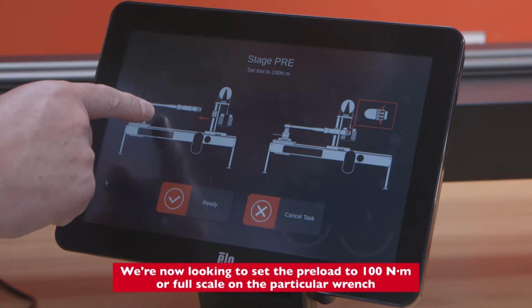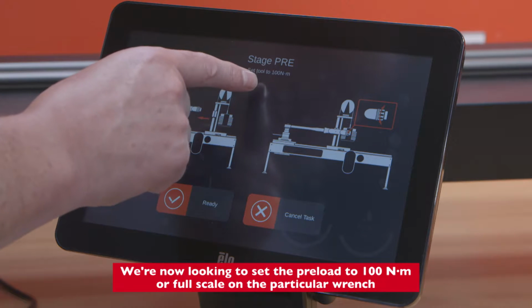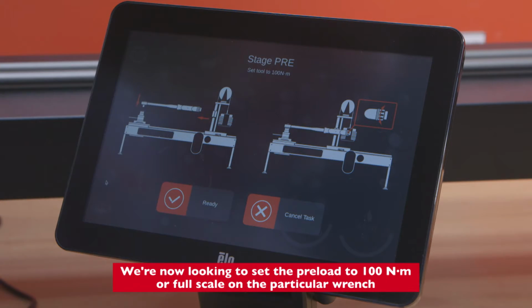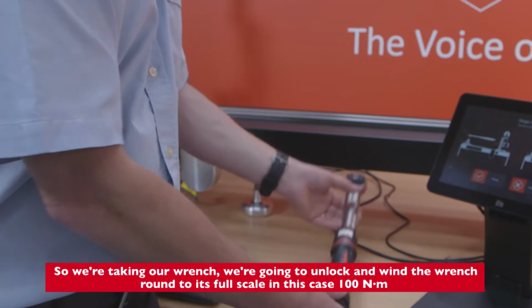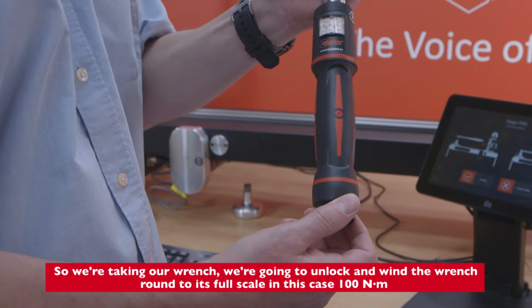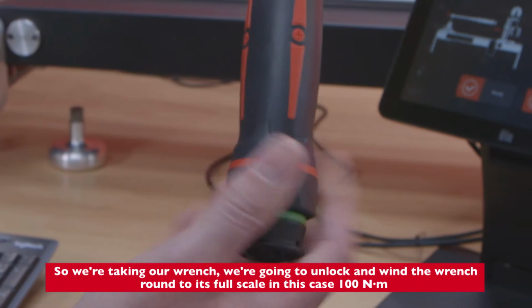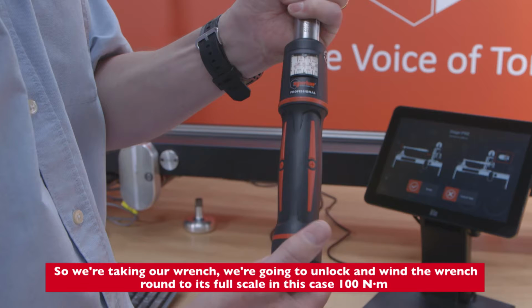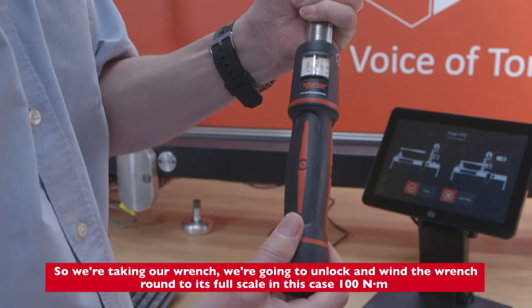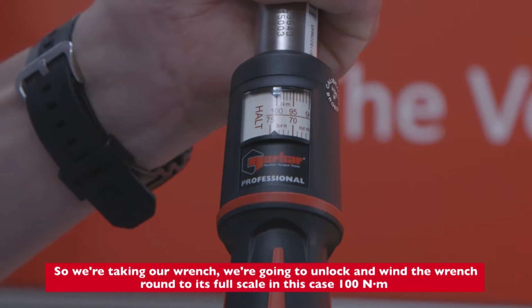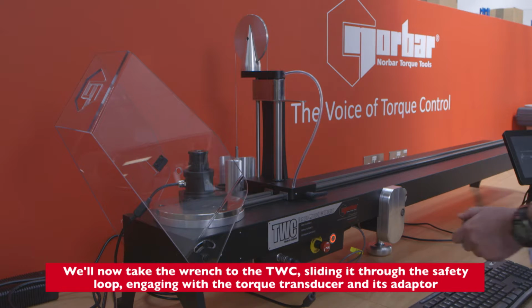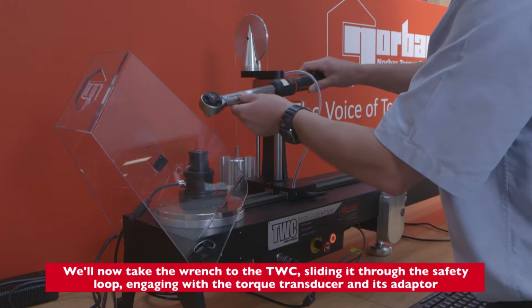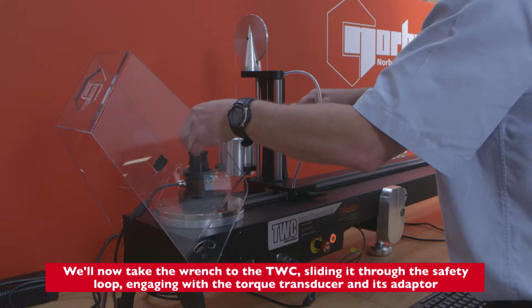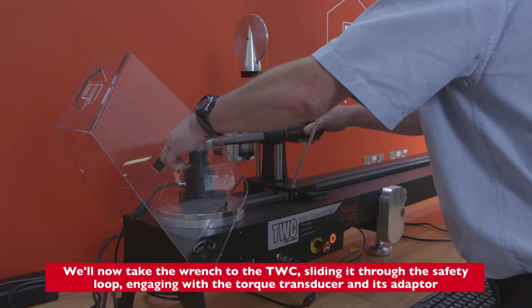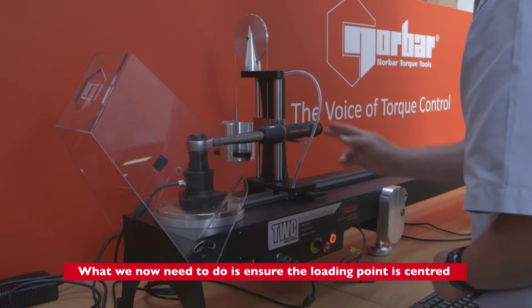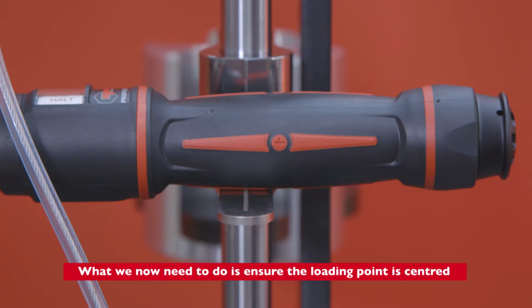We're now looking at setting the preload to 100 Newton meters or full scale on the particular wrench. So we're taking our wrench, we're going to unlock and wind the wrench around to its full scale, in this case 100 Newton meters. We now take the wrench to the TWC, sliding it through the safety loop, engaging with the torque transducer and its adapter. What we now need to do is ensure the loading point is centered.